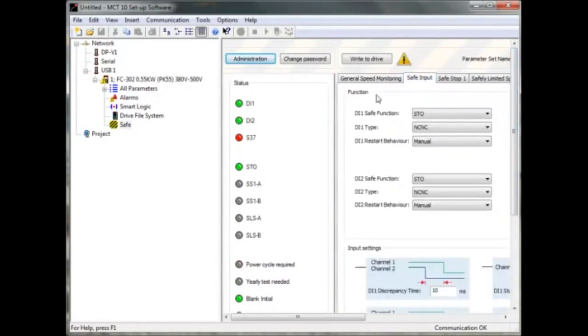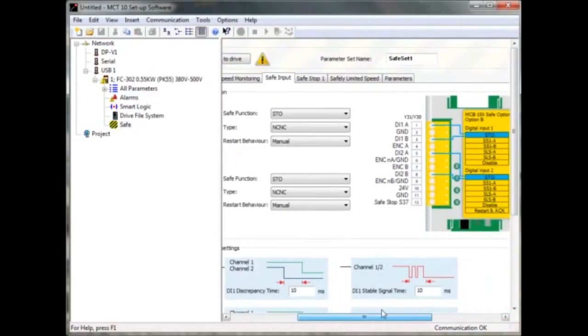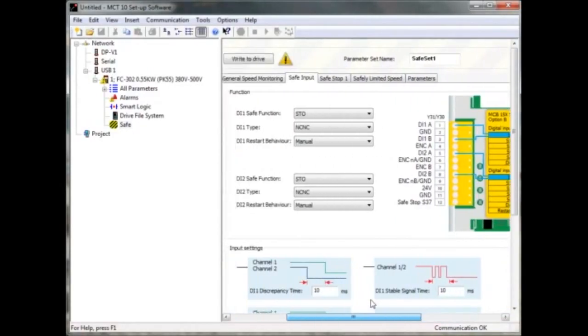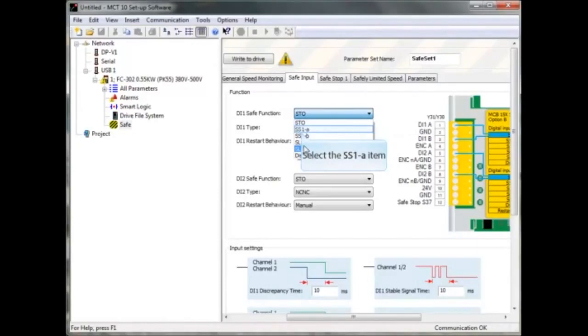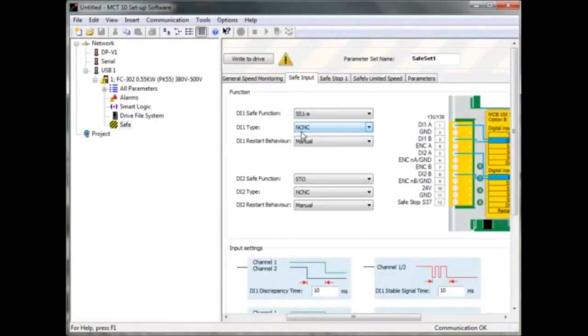In the next sheet, you choose your functions for digital input 1 and 2. The functions available on the MCB150 are STO, SS1, or SLS, which you select here. The contact type you can choose is NC/NC, or NC/NO, or normal NC.